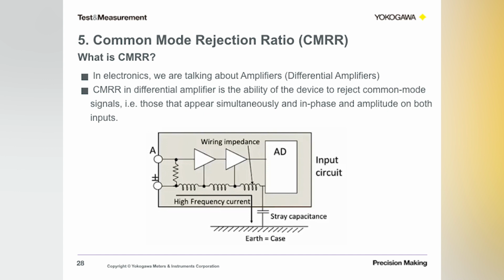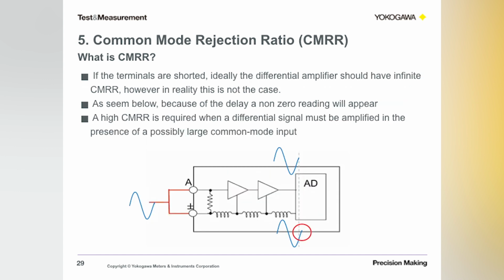and current. So as you can see from this diagram, the high potential path and the low potential path are different, and hence they will constitute different characteristics and have different uncertainties related to that. Now, if you were to short the input terminals and apply a signal, you'll notice that the signals will arrive at the A to D input at different times. Ideally, the reading should be zero, meaning it will have infinite CMRR, but because of the unequal delay due to the design, a non-zero reading will appear. And I'm sure you have observed this many times, and you've done testing on your input to make sure it's working or not working.